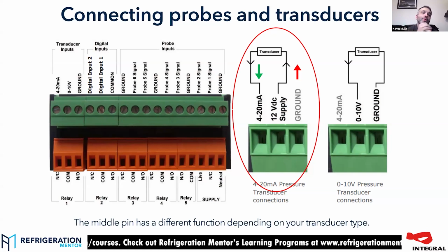Just talk a little about what you're going to connect to these controllers. So circled there is the plug for the transducer, as you can see on the main drawing on the left-hand side of it. Now, RDM by default likes to use 4 to 20 milliamps for the transducers. Very, very standard thing in the industry.